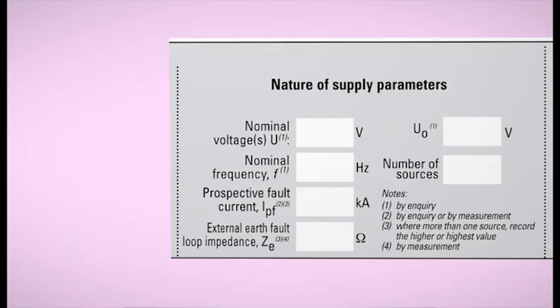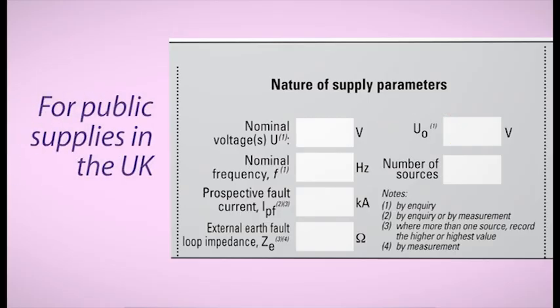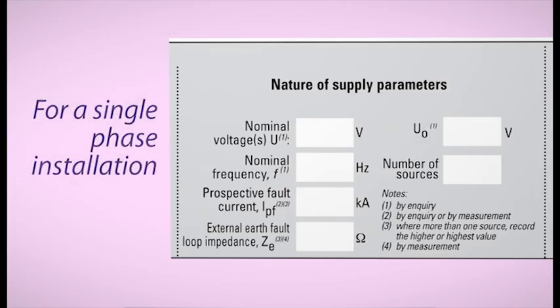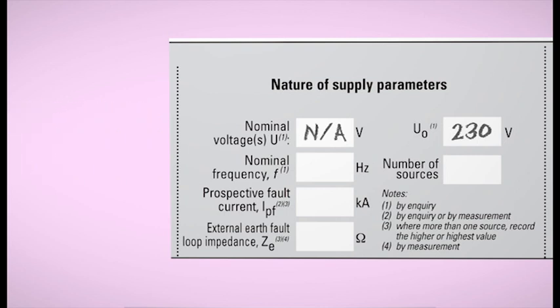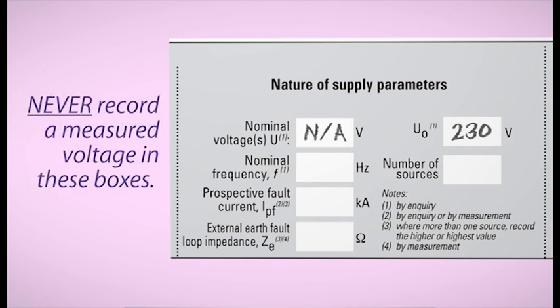As we can see, there are two boxes with nominal voltage written next to them, one identified with U and the other with U0. For public supplies in the UK, U is 400 volts and U0 is 230 volts for two-phase and three-phase supplies. For a single-phase installation, U should have not applicable and U0 should have 230 volts. And remember, you must never record a measured voltage in these boxes.